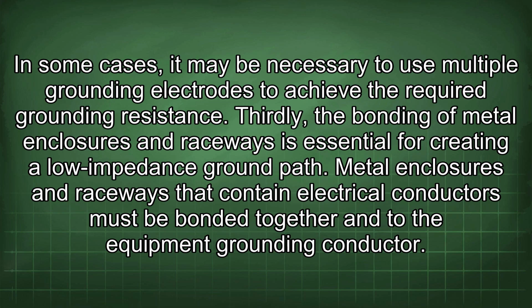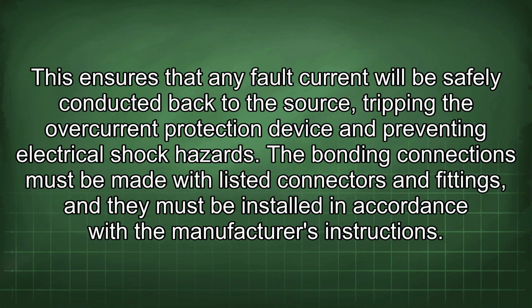Thirdly, the bonding of metal enclosures and raceways is essential for creating a low-impedance ground path. Metal enclosures and raceways that contain electrical conductors must be bonded together and to the equipment grounding conductor. This ensures that any fault current will be safely conducted back to the source, tripping the overcurrent protection device and preventing electrical shock hazards. The bonding connections must be made with listed connectors and fittings, and they must be installed in accordance with the manufacturer's instructions.